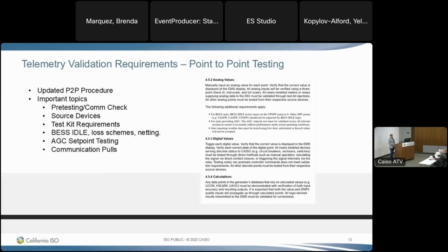We go into greater detail about the source device requirements, and that would be for both value and quality, right? So we look at specifically what types of devices are going to require test kit testing, and that would be for situations where we have our megawatt, megavar analogs, and then our discrete points like circuit breakers. Basically, anything that's coming from a relay or breaker, we want to test that from the source. We want to test that as realistic a scenario as we could, because that's going to ultimately make sure that when this resource goes sync, there's no surprises. Sometimes we've seen, for a resource where this wasn't tested correctly, they go sync, and then the megawatt, megavar points are reverse polarity, and the generation operators are on our GDSC line asking us what's going on, right? So this will really help clear out some of that ambiguity.